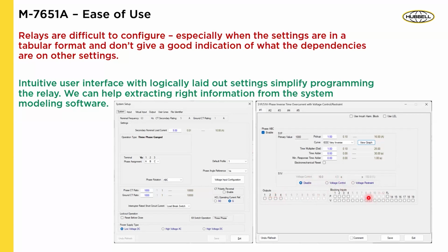And then there's inputs and outputs. I mean, the outputs and the blocking inputs are obviously laid out separately, so you can easily see which one is selected there. And this is consistent throughout all of our elements, right? So you would see the enabling over here, you'll see the outputs and the blocking inputs here, you'll see inrush restraint, and you'll see visual cues as to how to configure this.